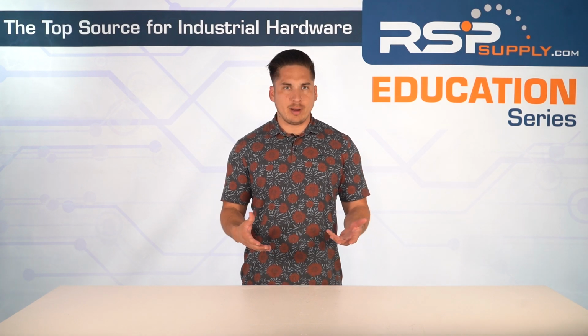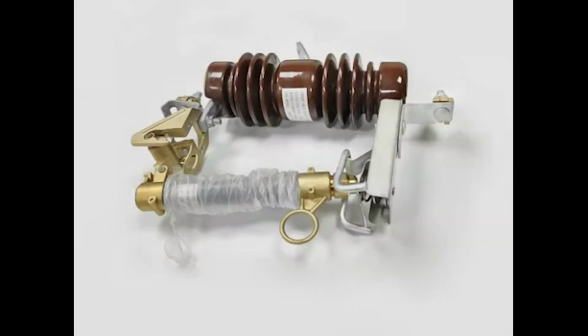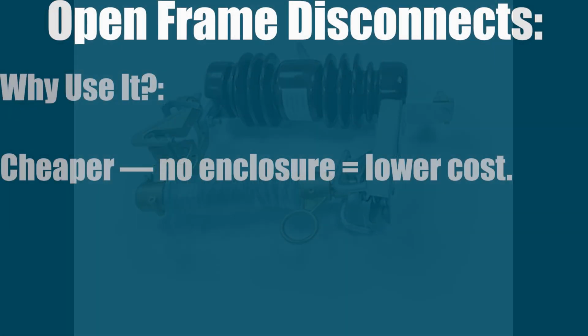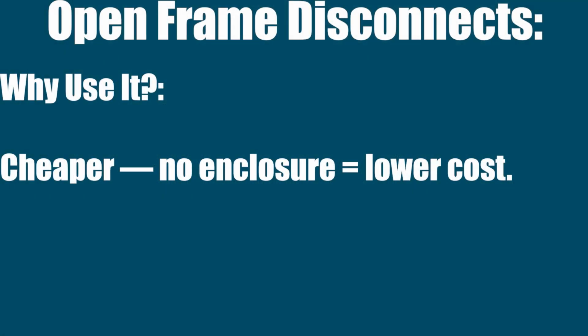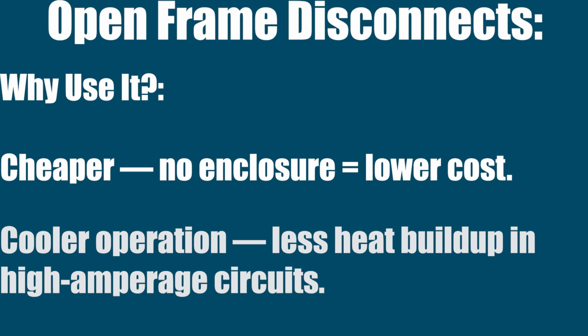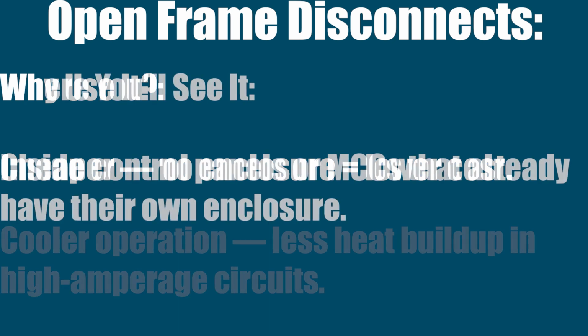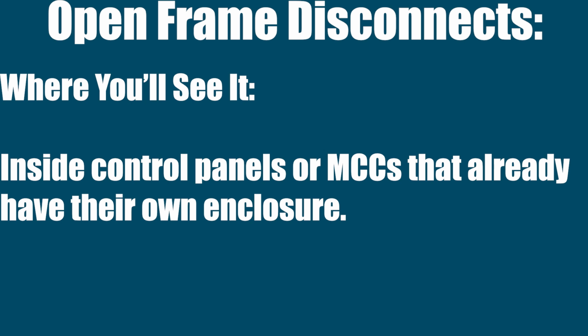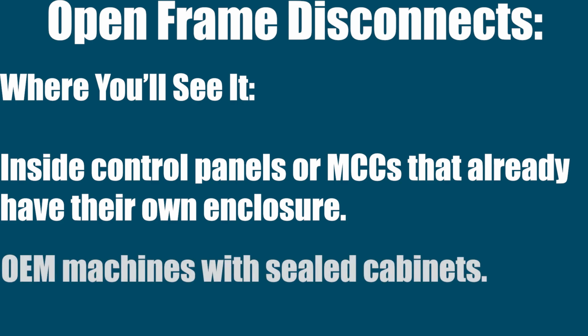Then you got open frame disconnects. These are just the switch guts, no box. Why would you use that? Well, it's cheaper. There's no enclosure, so it's a lower cost. It does allow cooler operation since there's less heat buildup in high amperage circuits. You'll see it inside control panels or motor control centers that already have their own enclosure. You'll also see them in OEM machines with sealed cabinets.